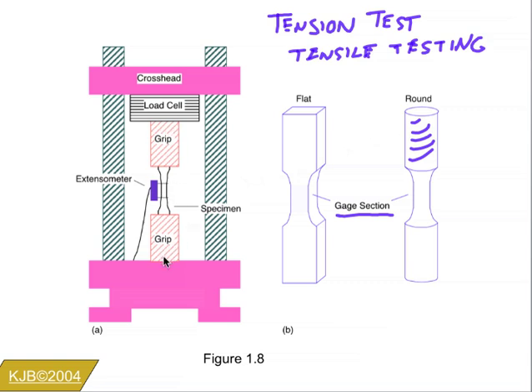And within this length including the grips, we can set up tension or compression by actually translating this crosshead, which is connected with threads coming down here, so this crosshead can move up or down. If the crosshead moves up, it's going to pull on the sample at the same time that it actually applies a load onto its threads.